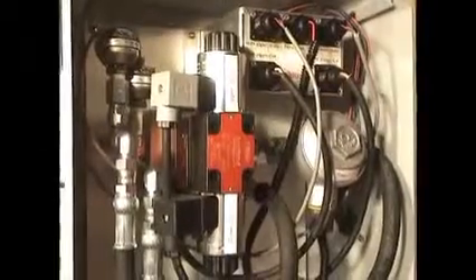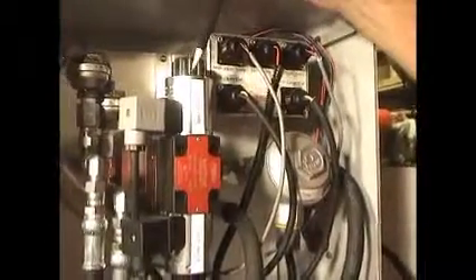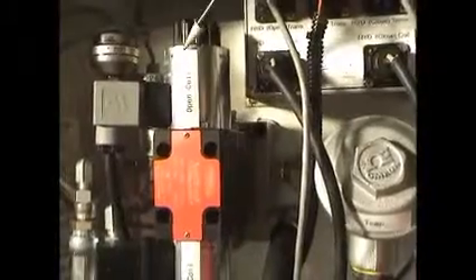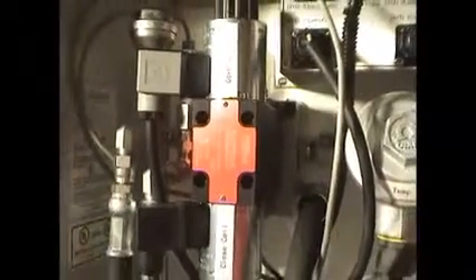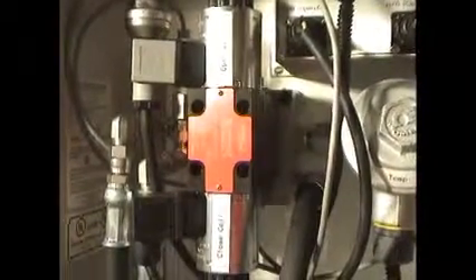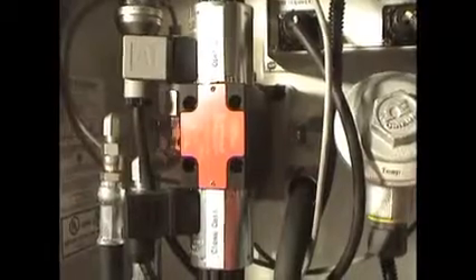Inside the enclosure are the following components: a proportional valve, a pressure compensated valve, a check valve, and a base plate with a pressure regulating valve mounted at the base of the base plate. A variable electric current to either the open or the closed coils of the proportional valve directs oil flow to the hydraulic cylinder attached to the butterfly valve.